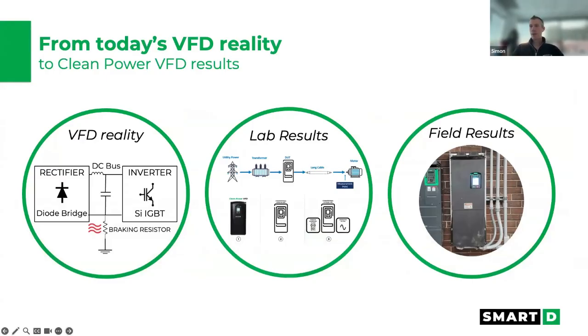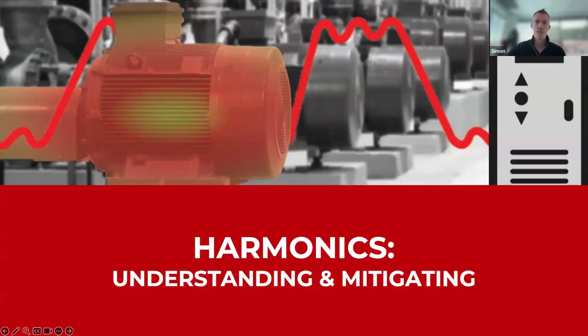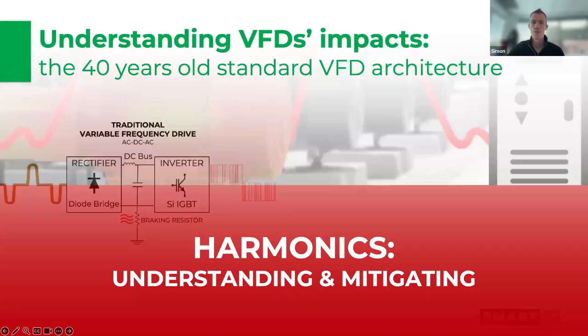Those were done by a third-party lab where they had a dedicated motor test bench with long cables, about 500 feet, and a dedicated transformer to mimic a very stiff grid, comparing our clean power VFD, a standard 6-pulse drive from a leading manufacturer, and that same 6-pulse drive with a passive harmonic filter and sine wave filter. And then I'll refer throughout the presentation to different field results and case studies. So let's dive into it right away, focusing on harmonics to start off with.